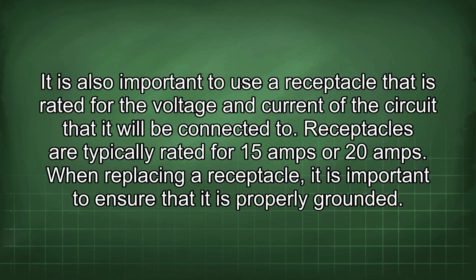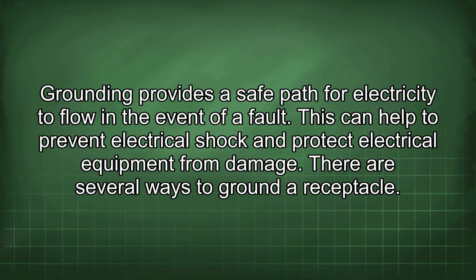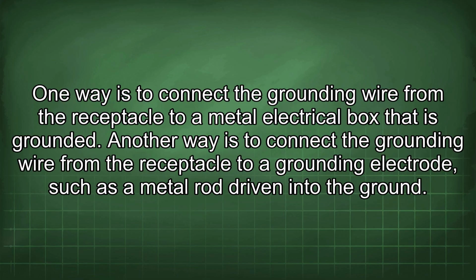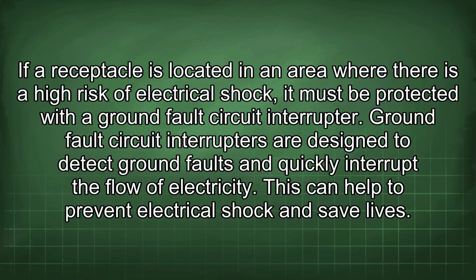When replacing a receptacle, it is important to ensure that it is properly grounded. Grounding provides a safe path for electricity to flow in the event of a fault. This can help to prevent electrical shock and protect electrical equipment from damage. There are several ways to ground a receptacle. One way is to connect the grounding wire from the receptacle to a metal electrical box that is grounded. Another way is to connect the grounding wire from the receptacle to a grounding electrode, such as a metal rod driven into the ground.